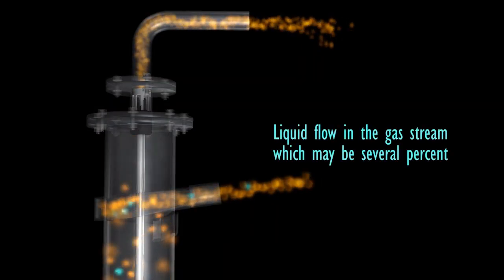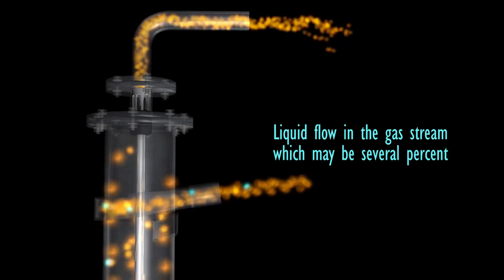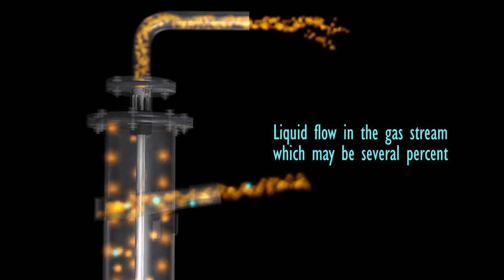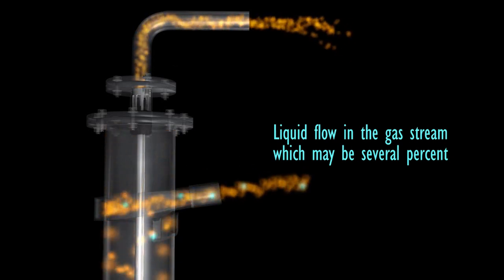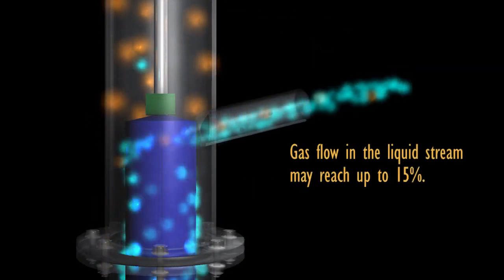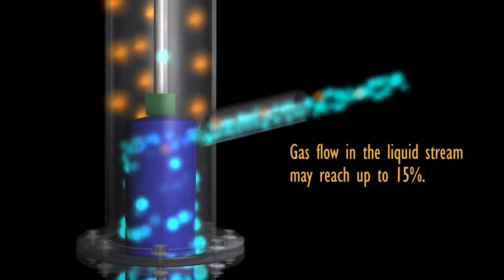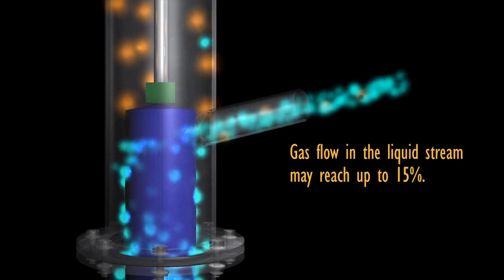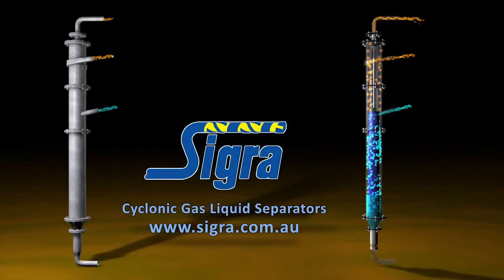The separator has the ability to handle a liquid flow in the gas stream which may be several percent and may come in slug form. The gas flow in the liquid stream may reach up to 15 percent. Sigra cyclonic separators come in a variety of sizes and with varying nozzles to suit different flow ranges.